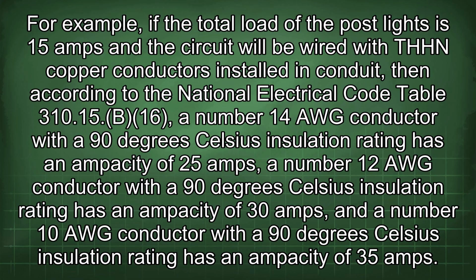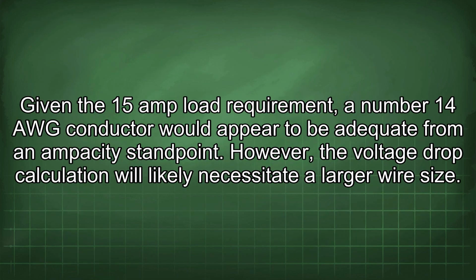A number 12 AWG conductor with a 90 degrees Celsius insulation rating has an ampacity of 30 amps, and a number 10 AWG conductor with a 90 degrees Celsius insulation rating has an ampacity of 35 amps. Given the 15 amp load requirement, a number 14 AWG conductor would appear to be adequate from an ampacity standpoint. However, the voltage drop calculation will likely necessitate a larger wire size.